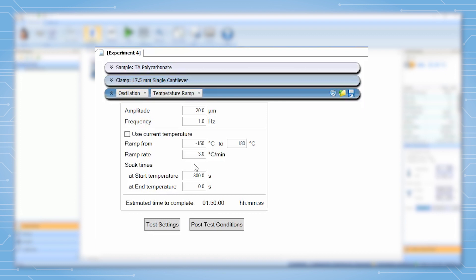Typically it is chosen to be between 1 and 5 degrees C per minute. This allows the sample to remain in thermal equilibrium with the current temperature during the temperature ramp test.